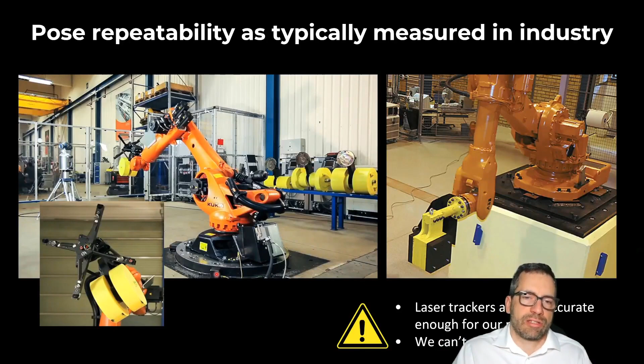As you can see here, all these 5 points are very, very different. One is here, one is here, here, here, and here. And we don't use the exact norm for this measurement that I made in my lab, because again, you're supposed to go from P1 to P2 in a straight line, but with this kind of device, you cannot. You have to retreat and then approach P2. But even this way, we get the same results as the ones specified by the manufacturer. As you can see, P1 or P5 or P3, it's pretty much the same repeatability, between 9 and 12 micrometers. So where you measure the repeatability doesn't matter that much.